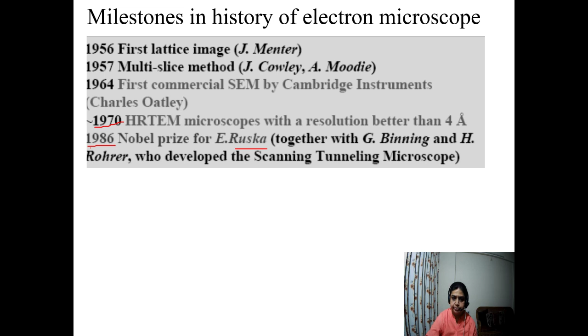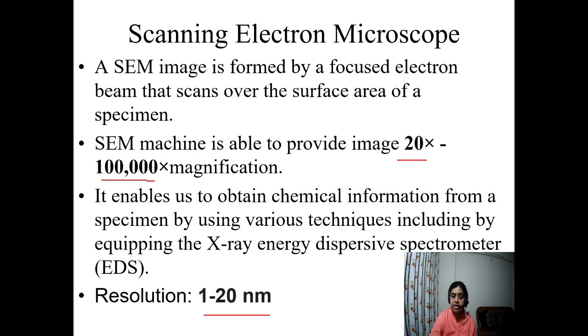Let's come to the scanning electron microscope. Basically, SEM image formation is done by a focused electron beam that scans over the surface area of the specimen. The SEM machine has very good magnification, from 20 times to 100,000 times. The important thing is that it can give us compositional analysis as well. SEM has a resolution around 1 to 20 nanometers. However, in the TEM, it can go up to 0.5 nanometer as well. We will come to the TEM later on. So let's start with the instrumentation.